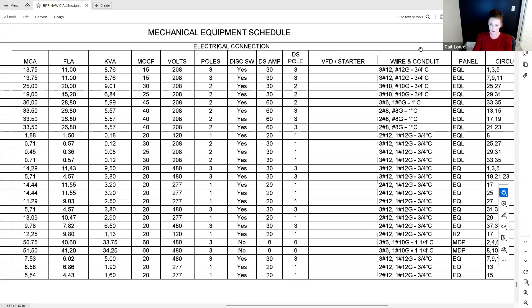and all this other stuff, blah blah blah, I don't care about. I'm looking at your wire and conduit. It literally tells me what it goes from - so 1 1/4 inch conduit, 3 number 6s, and 1 number 10 ground. It's going from MDP to, and it'll tell you the panel, the Y. I don't really care about the Y right now, but it gives you the circuitry information. What you're really looking at, what your electrical contractor is really looking at, is the wire size, so we don't have to calculate it - that really is the engineer's job.